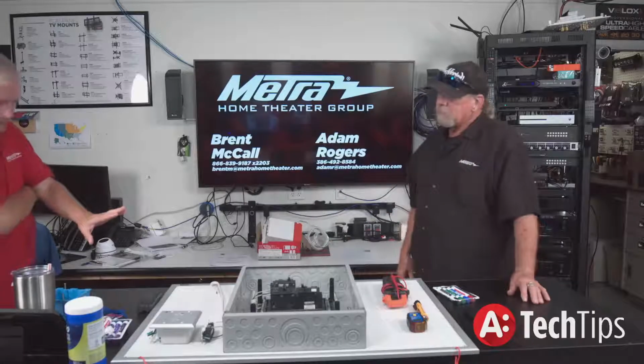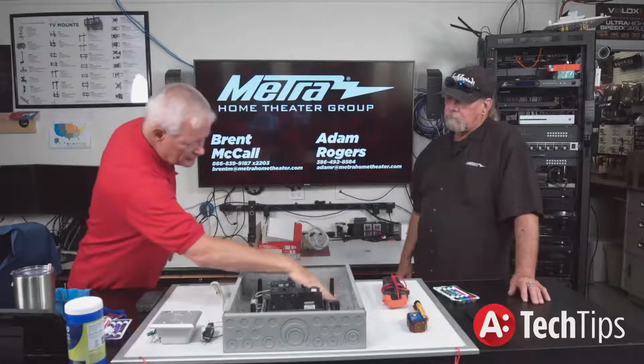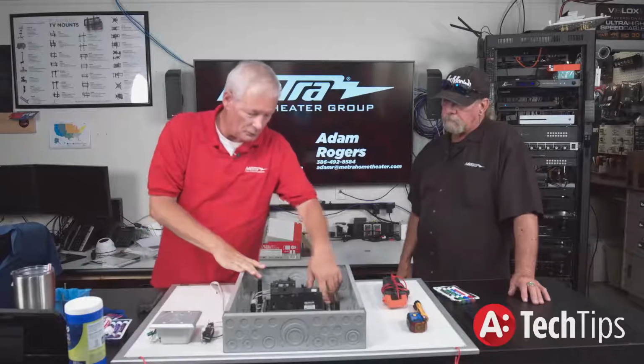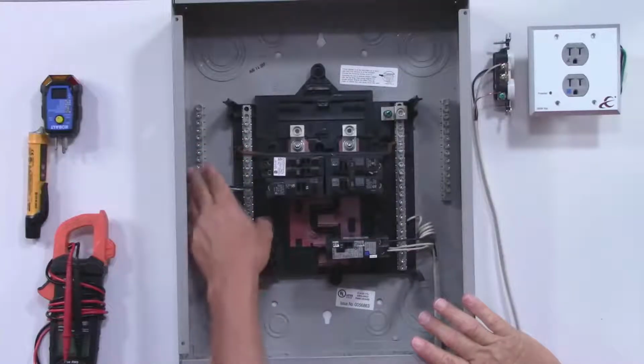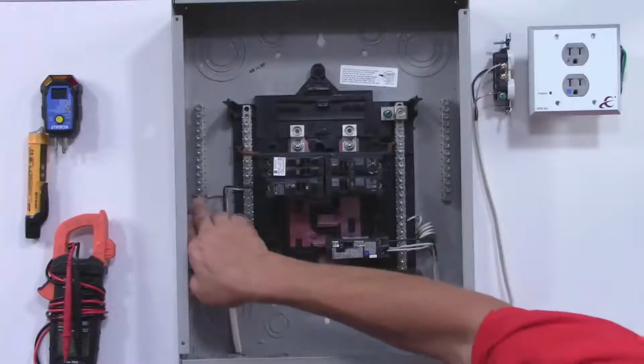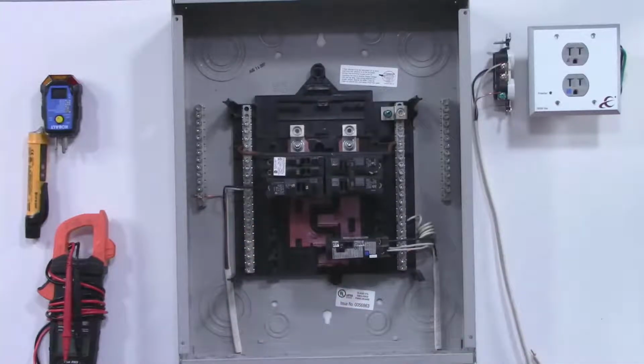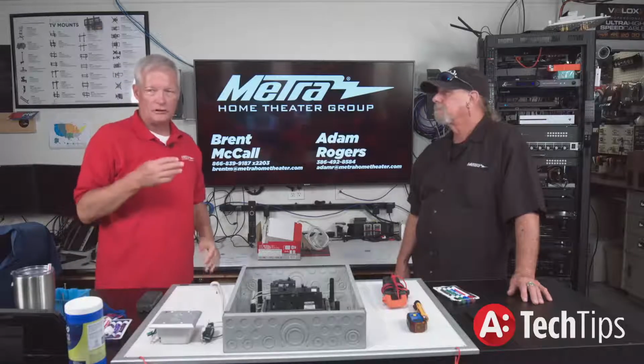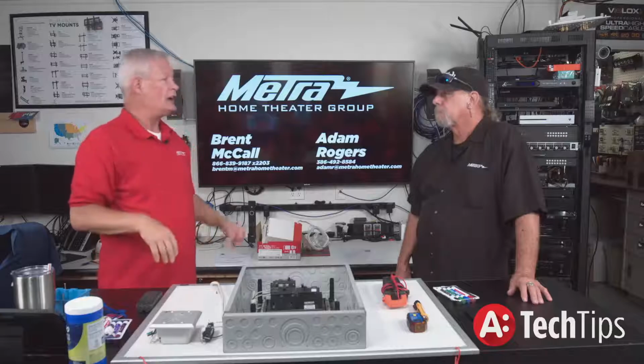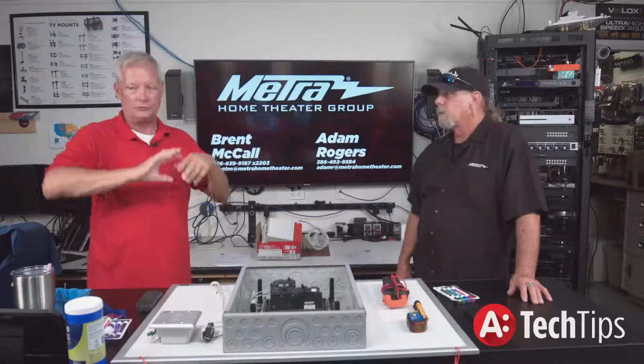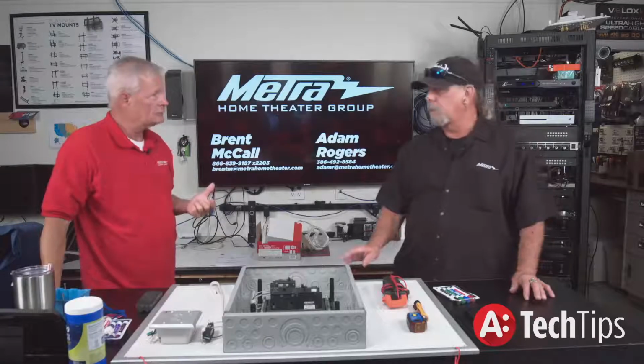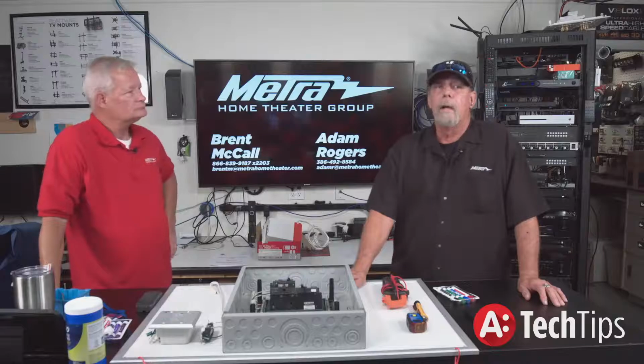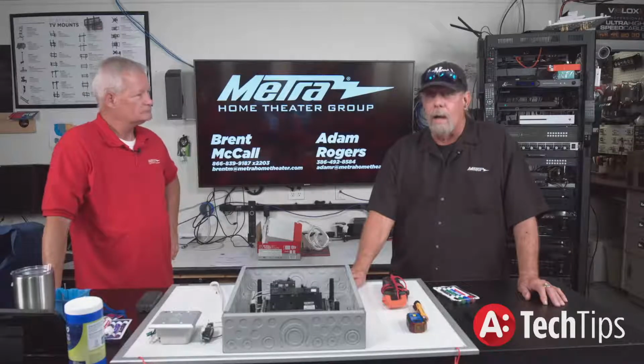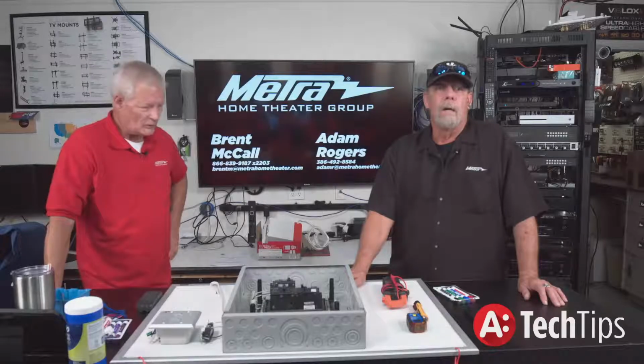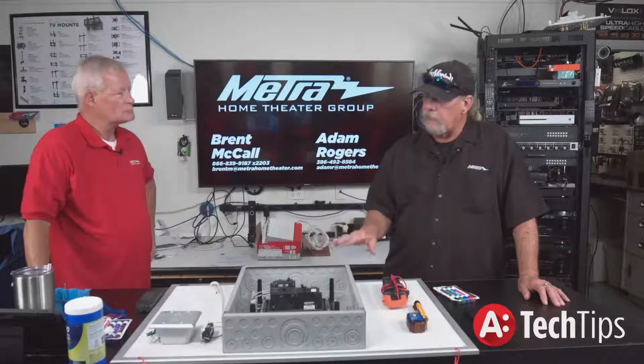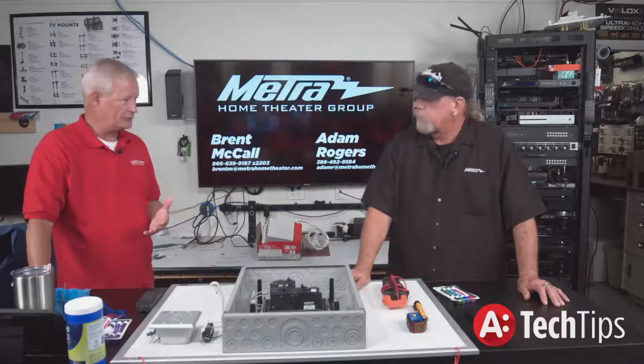Staying with the panel a minute - when you're looking at the grounding inside of this, you've got the neutral, which are all bonded together, and then the separate ground. Ultimately, these are tied together going out to the street, or is this separate? They are tied together at the first means, when they first come into the house. Coming into the house, you're going to see typically 3 feeds - 2 blacks, and generally an aluminum wrapped, not braided, just bare aluminum, which is the neutral coming from the power company. And then we always run a copper wire out for a ground to a ground rod or structural steel, something that'll take with the house. That is the earth ground for the house.